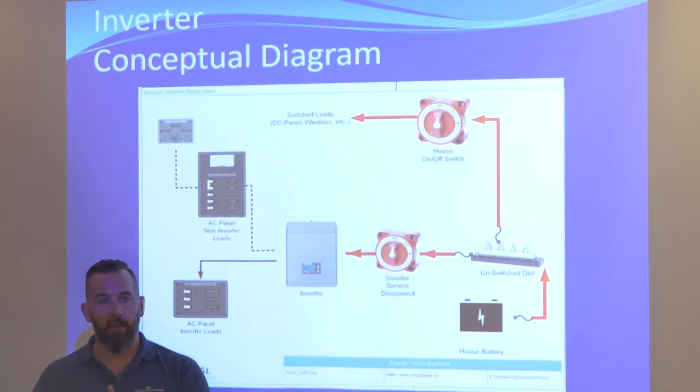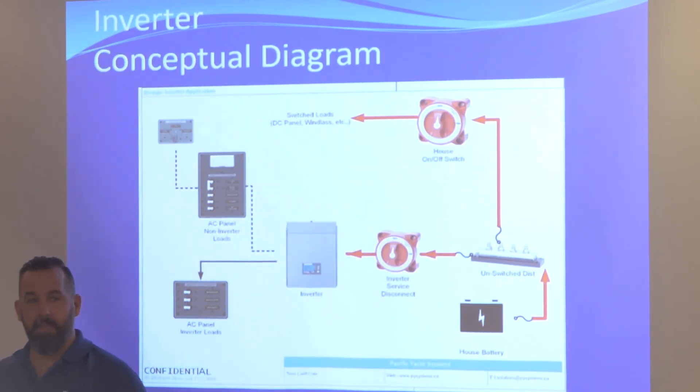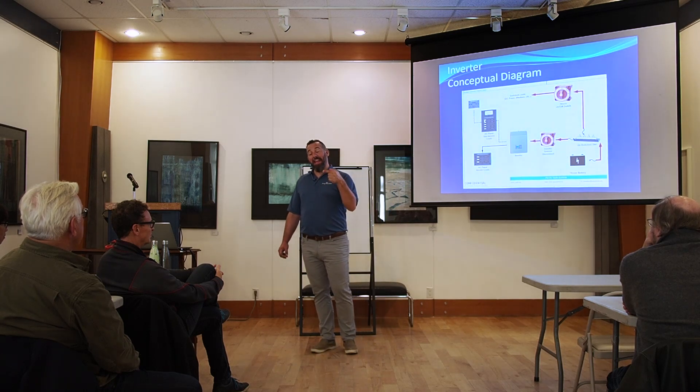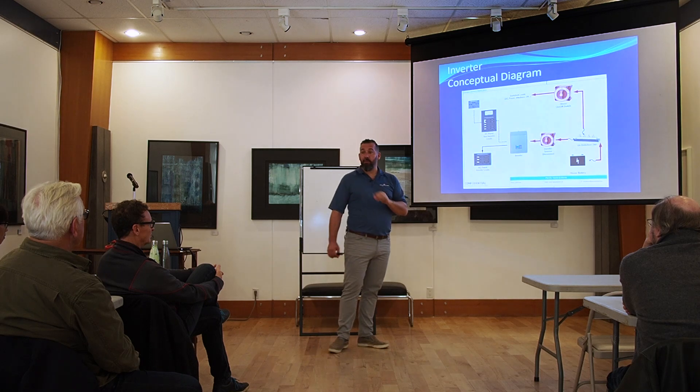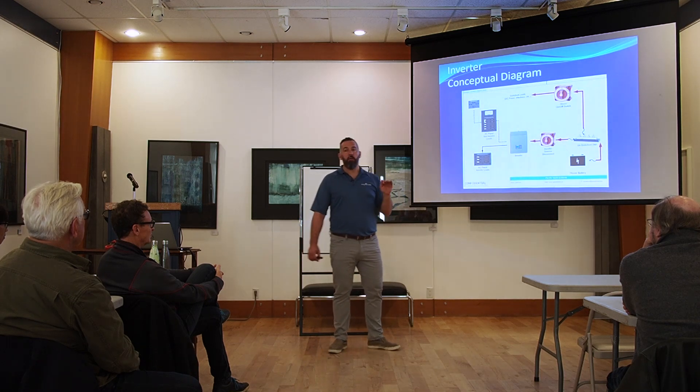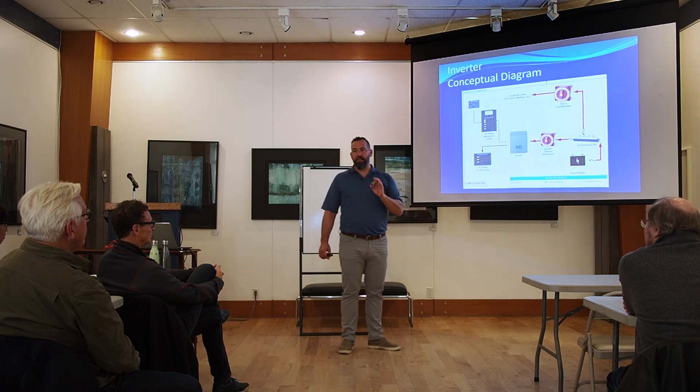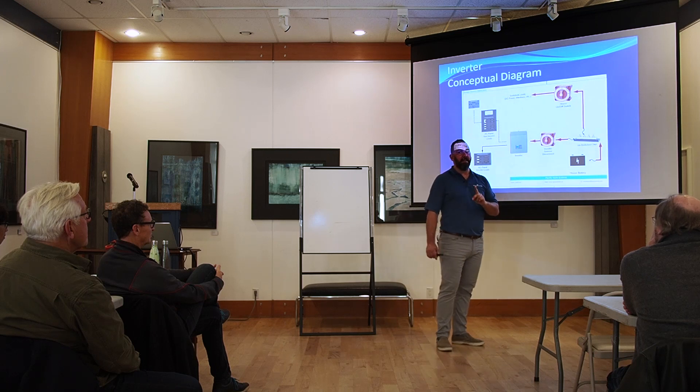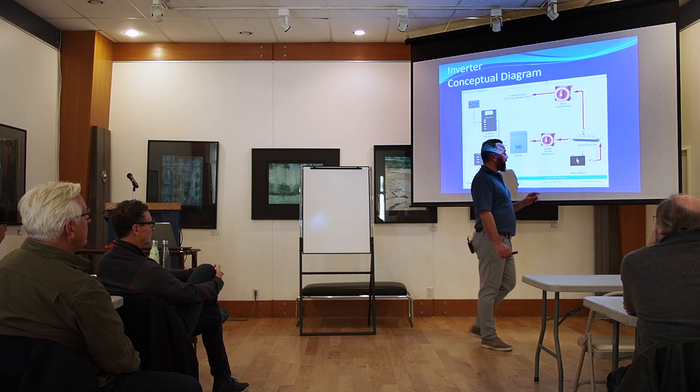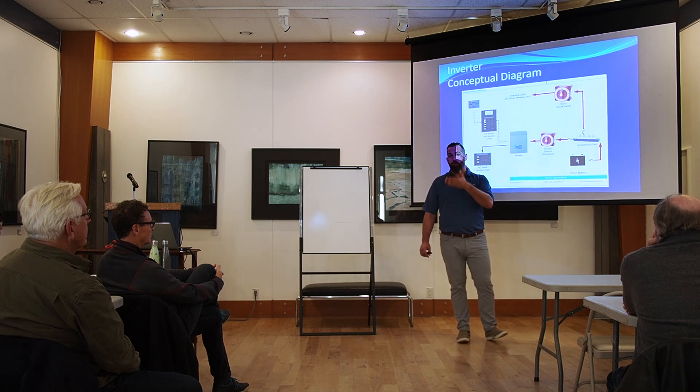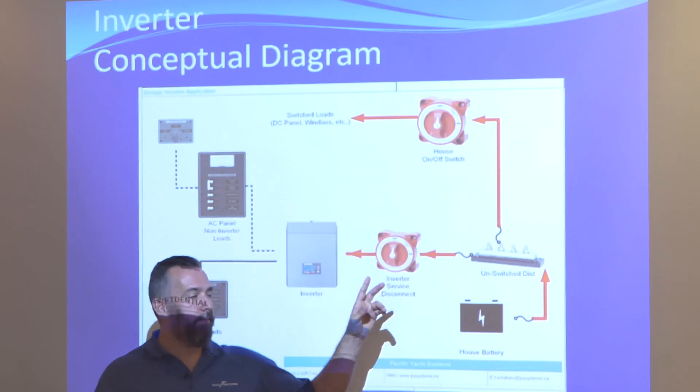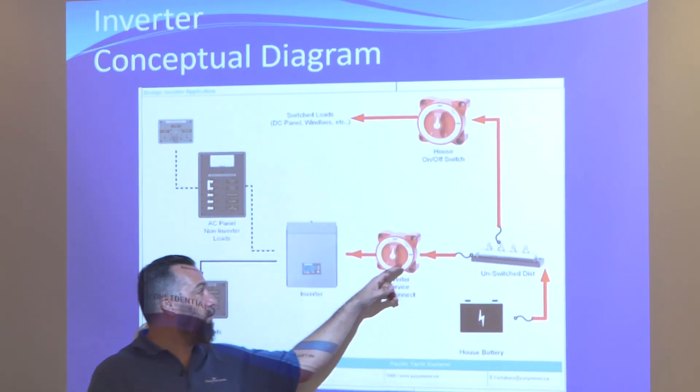Make sure the connection is done perfectly. Remember, stainless steel is not conductive. That fuse has stainless steel washers. If you put that stainless steel washer between the fuse holder and the fuse, you will melt that fuse holder down. Stainless is like four percent conductive. It's not a conductive material like copper. Make sure the washers are in the exact same order they were in. This is very important. Change that fuse, turn the switch back on, and this should light up.